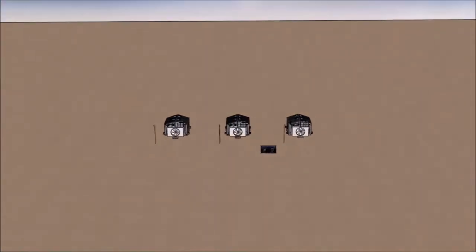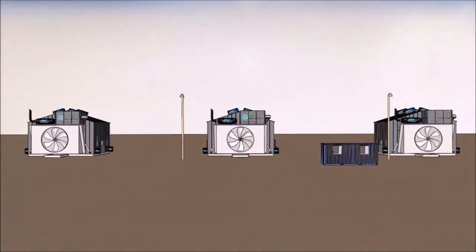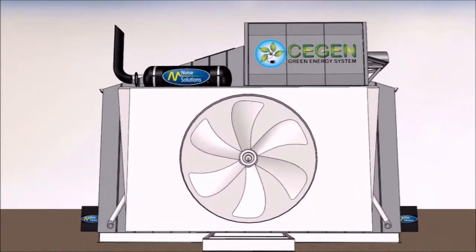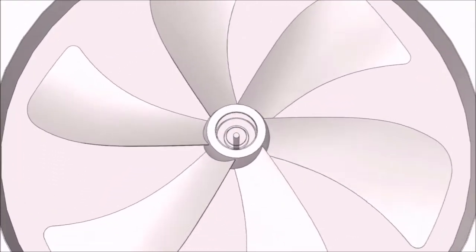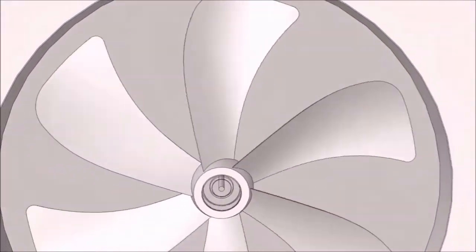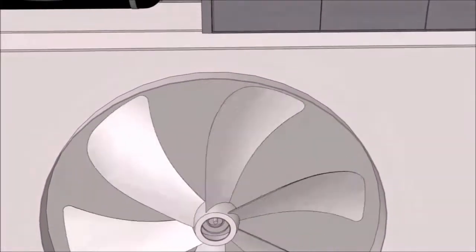On a typical 1500 horsepower gas compressor, the exhaust wind of the vertically positioned cooler fan will enable the CEGEN unit to produce approximately 6 to 8 kilowatts per hour of green power with less than 0.2 IWG added to the static pressure.